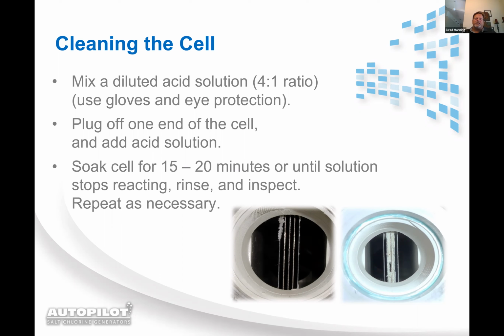And then one of two things has happened. If it stopped bubbling, it means that either all the calcification has been removed or the acid is so saturated it can't absorb any more. So you're going to dump the solution out. I advise you to take it to the pool and dump it in the pool because the pH needs to be lowered. You're going to check the cells to make sure they're clear of calcium, and if not, you're going to repeat the process. After it stops bubbling, you've checked them and they're all clear.